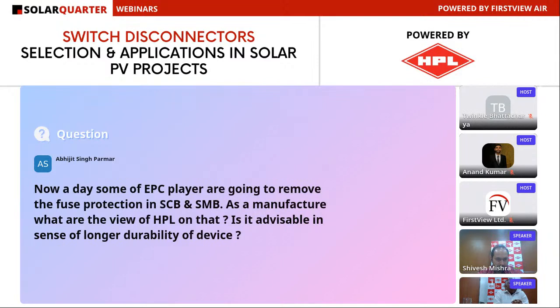As far as my point of view is concerned, any disconnector, whether manufactured by HPL or by somebody else, is meant for switching power supply on and off. It doesn't provide protection. So personally, or on behalf of HPL, I would suggest that we should use fuses as a safety device. Otherwise, if we don't use any protection, it can lead to problems, and the system will not give you a durable and longer serviceable life. There will be a problem if any fault comes, and in solar and DC applications, surges and many other things keep coming. So it is better to always use fuses.